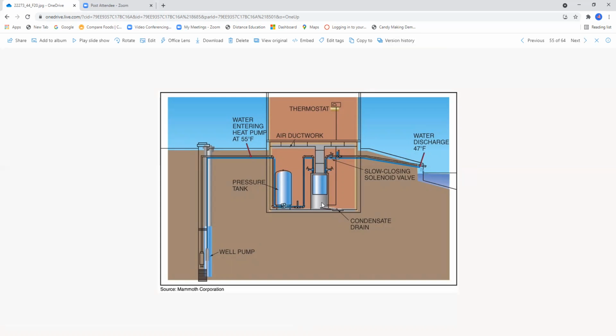Nothing mystical about this. The only thing that makes this different is the fact that we're utilizing a water source. In this case, we're utilizing a lake, stream, pond, or marsh discharge in the open loop heat pump in the heating mode. So this is going to be what you're going to see in the heating mode here.